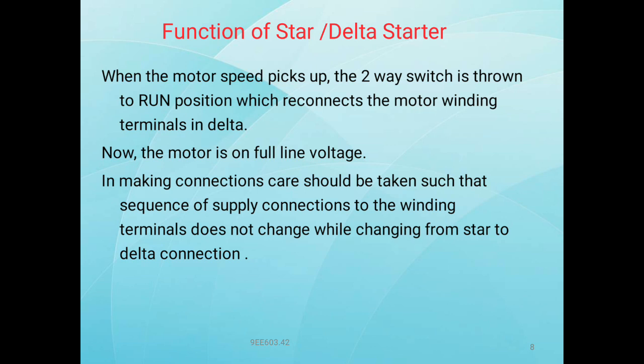In making connections, care should be taken such that the sequence of supply connections to the winding terminals does not change while changing from star to delta connections.